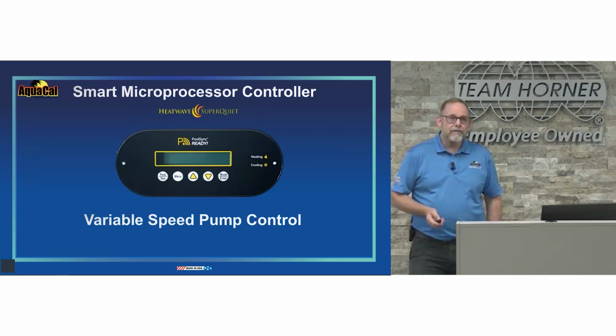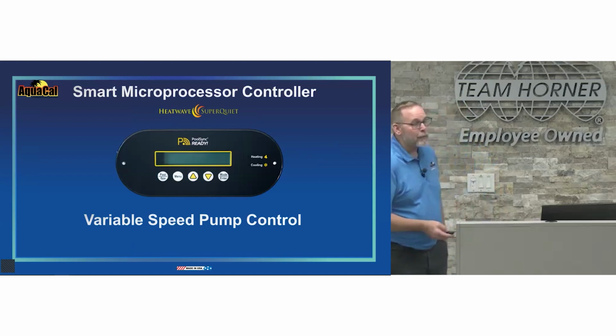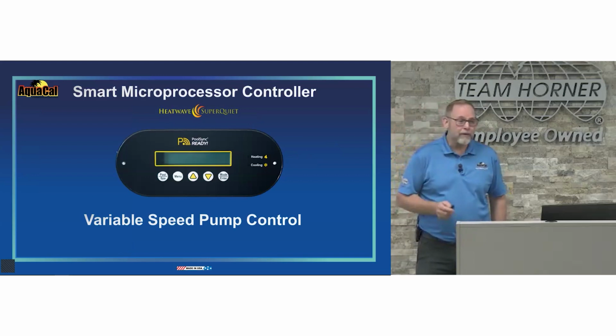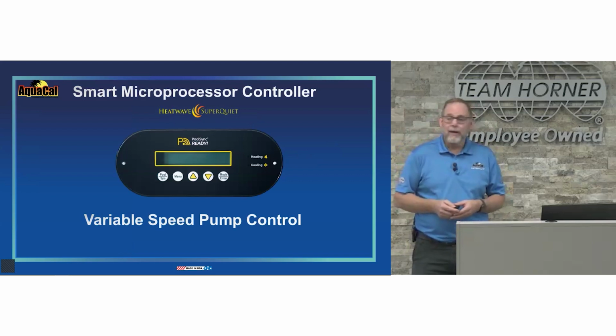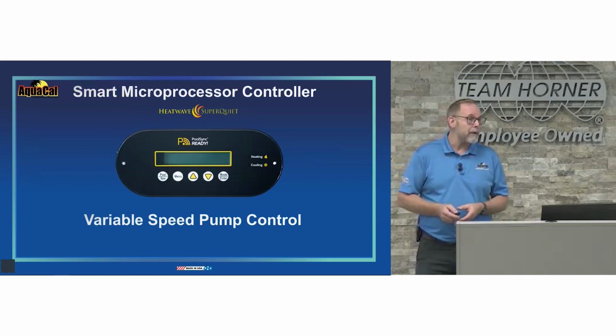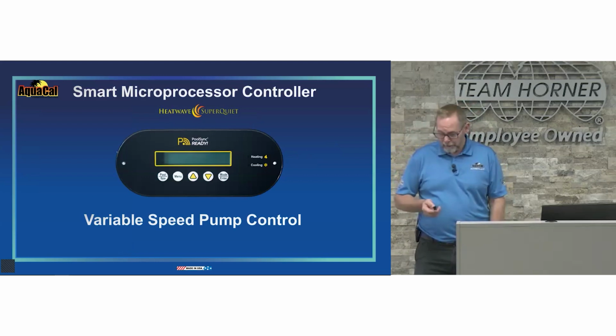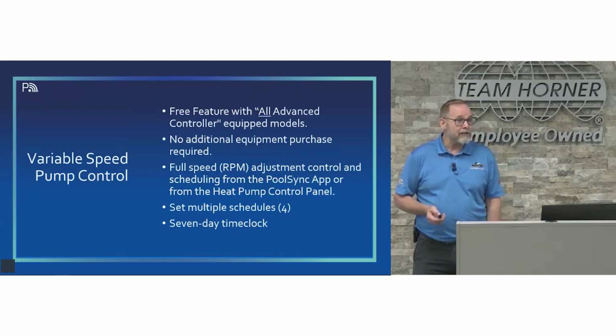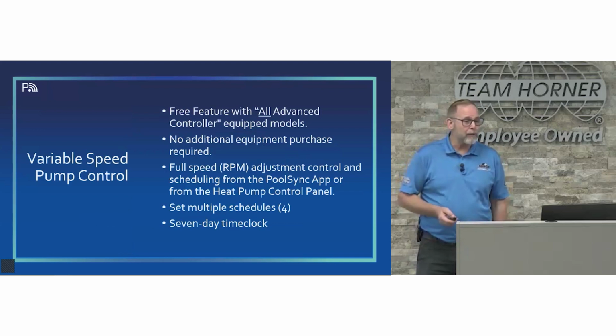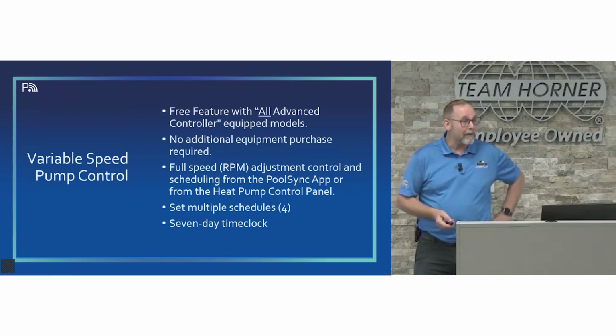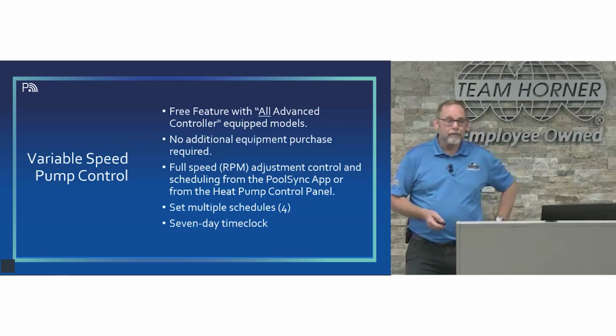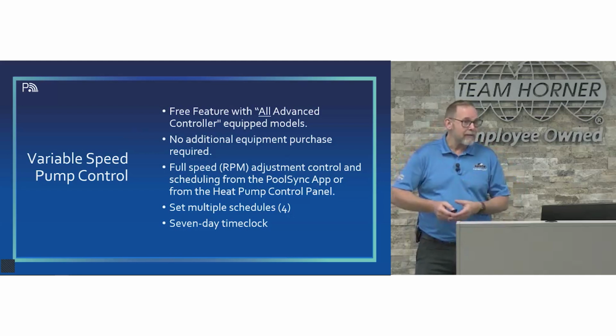So one of the features that we've had ever since we released the smart microprocessor, and this feature is available with or without the PoolSync antenna, is that any unit with the smart micro has variable speed pump control. A lot of people aren't aware that we have that feature. It's free, it's built in, you don't need to buy any additional equipment. So again, a free feature with anything with the advanced controller. We just connect it right up to one of the ports on the heat pump control board, and it gives us full variable speed pump control, scheduling of the pump. If you've got control of the pump, then you can schedule the whole system, the heating cycle. So we can do up to 4 schedules per day, and it's a 7-day time clock.